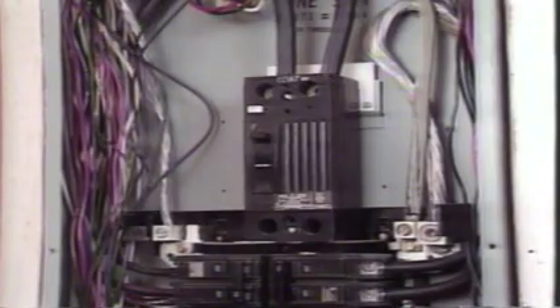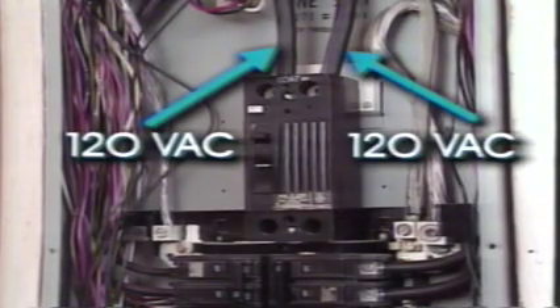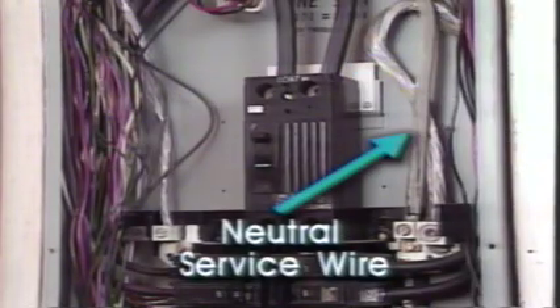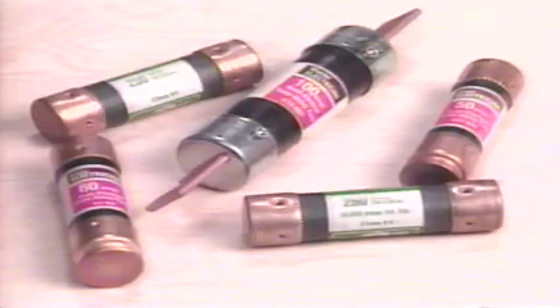Let's look at a typical residential distribution panel, one that uses circuit breakers. Power comes into the panel through two hot wires. Each wire delivers 120 volts. This is the supply current for the panel. There is also a third wire. This is called the neutral service wire. The two hot 120 volt wires are connected to the main breaker or fuse. This one is a circuit breaker, but it could be very large fuses. Main power fuses are usually cartridge type fuses. These come in many ratings and are usually installed as pullouts. This main breaker protects the panel and house wiring from receiving too much power. The main breaker has an on-off switch and is usually rated for 100 or 200 amps.